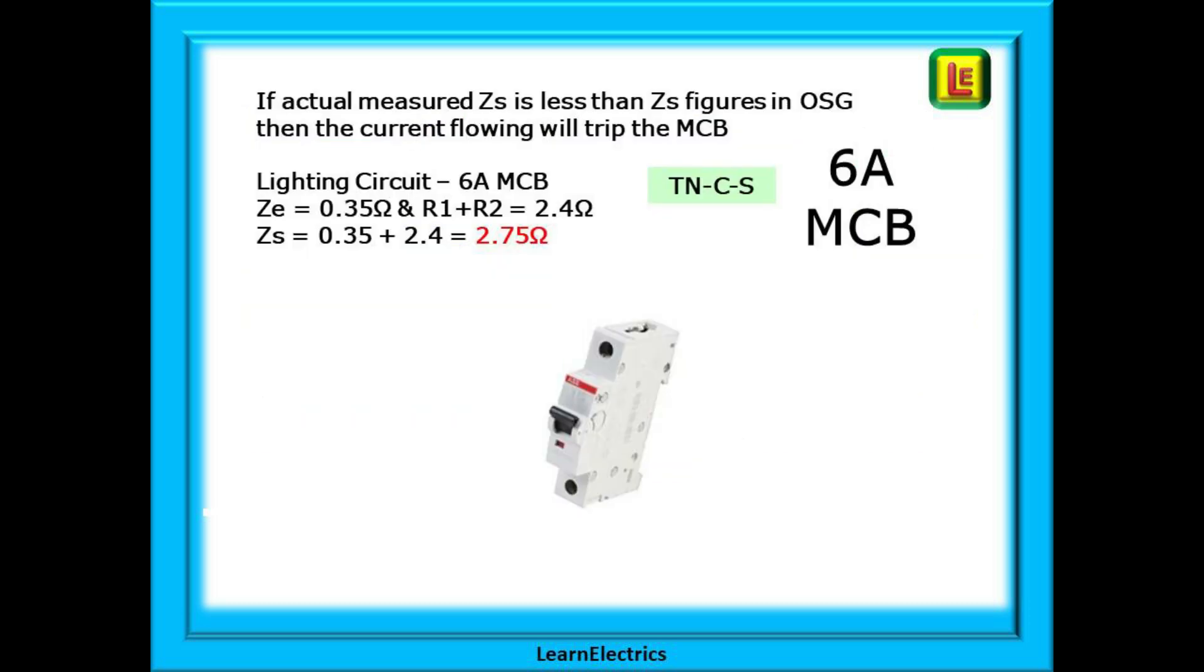The on-site guide will give us the maximum measured ZS values for different fuses and circuit breakers in table B6. If the actual measured ZS using our multi-function tester is less than the figures in the on-site guide then we can be confident that the breaker will trip in the required time for safety.